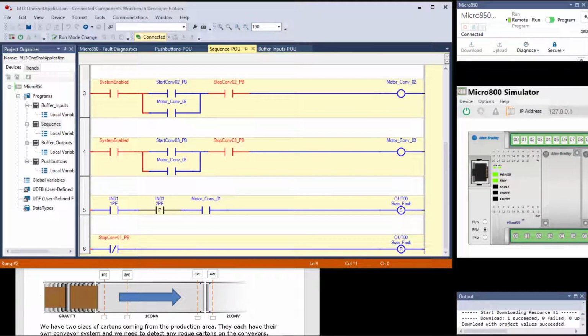So we're looking at rung number 5. You would have to go up and look at the conveyor rung to see if the conveyor stopped, but it should be stopped. Where is the conveyor stopped? Rung number 2. How would the operator clear the situation? Pulls out whatever the offending rogue carton was, hit the stop push button to reset it, and then hit the start button to get conveyor 1 going again.